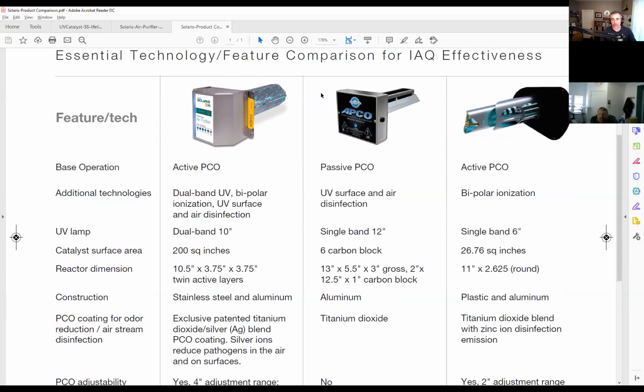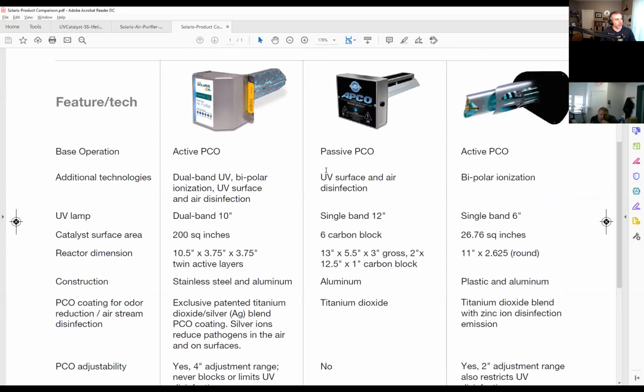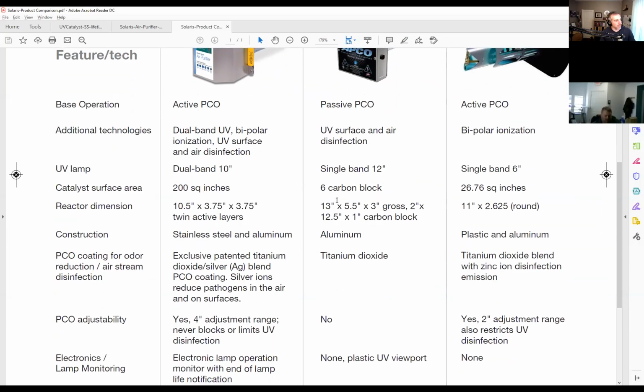And if I actually had my catalyst here next to the APCO, that would be listed as a passive PCO device because again, they have the carbon. Difference is carbon and metal both have the titanium dioxide on it - it's either you're going zero ozone or you're going for adjustability.